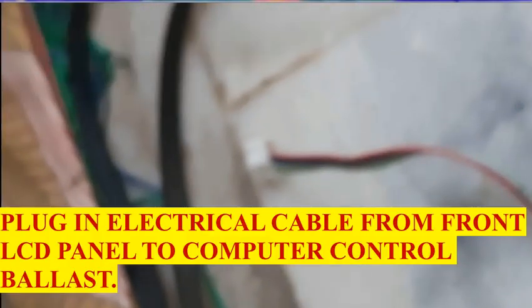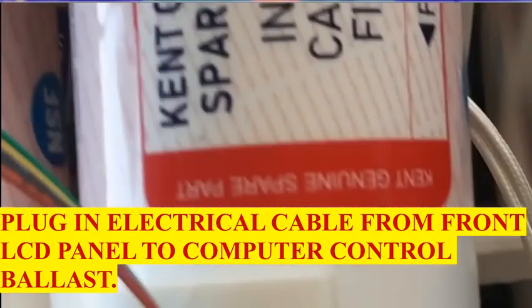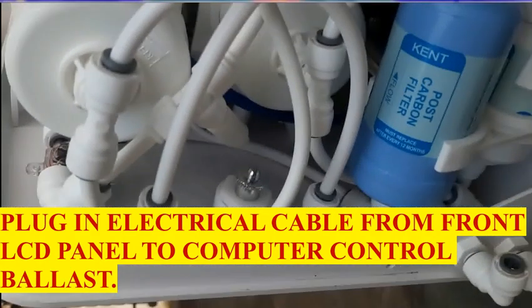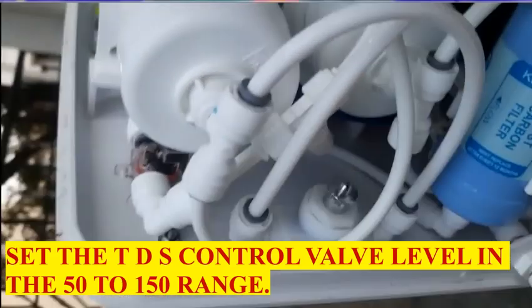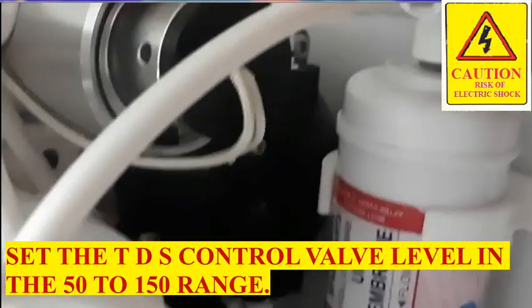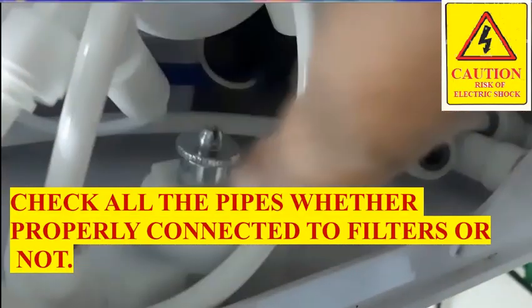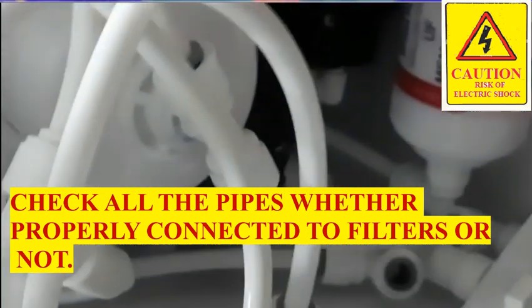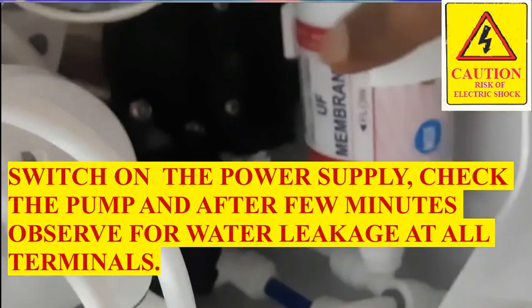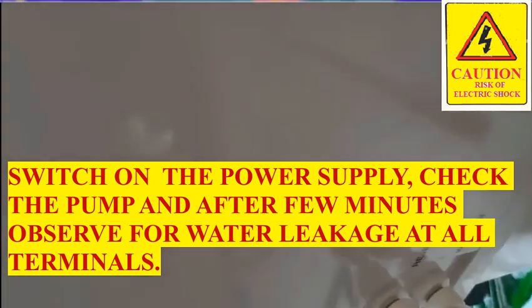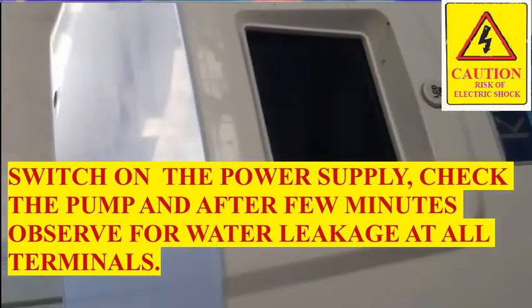Plug in electrical cable from front LCD panel to computer control ballast. Set the TDS control valve level in the 50 to 150 range. Check all the pipes whether properly connected to filters or not. Switch on the power supply, check the pump and after few minutes observe for water leakage at all terminals.